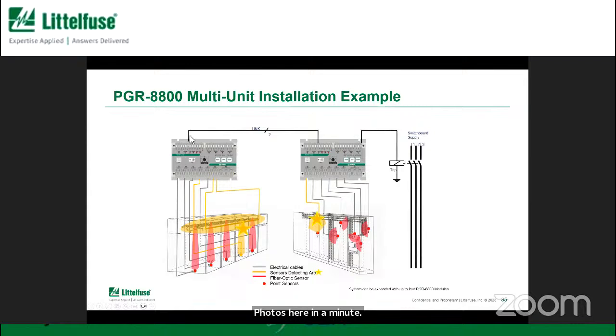So as I mentioned before, sometimes I think a picture helps to describe it. Here we show two PGR 8800 relays connected together. So if you have equipment where you need many sensors, that is no problem. You can connect all the sensors you need, wire the relays together, and this relay here can trip the breaker even if it sees a flash on this side. And this all happens still within the 1 millisecond time frame. So if we have an arc over here on the left, seen by this relay, it's transmitted to this relay, and this will trip the breaker. This trip signal will still come in 1 millisecond or less.